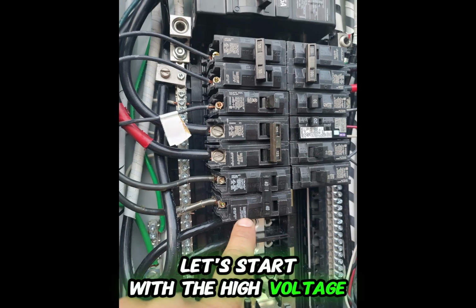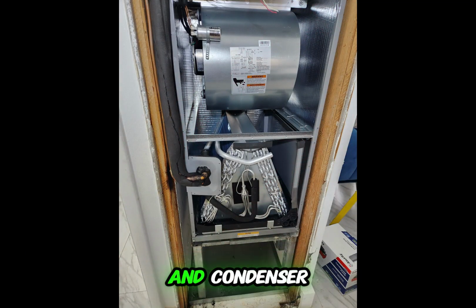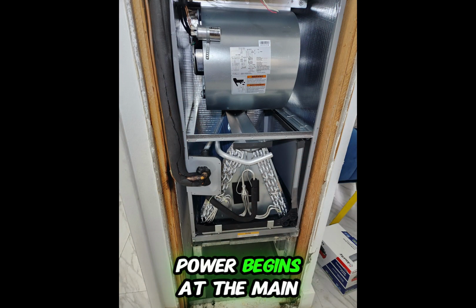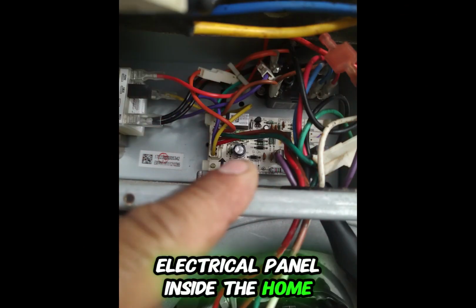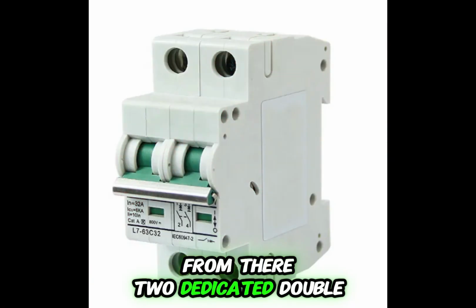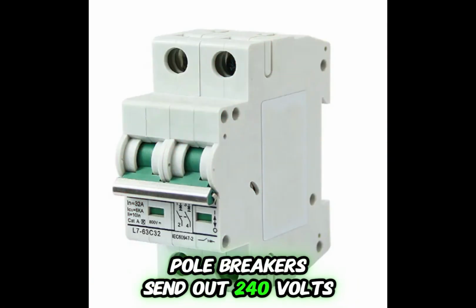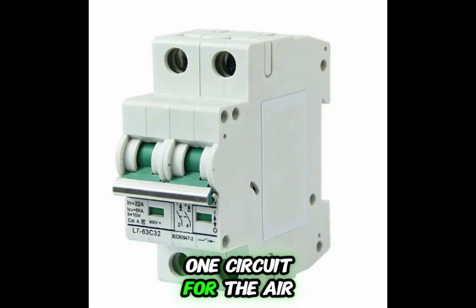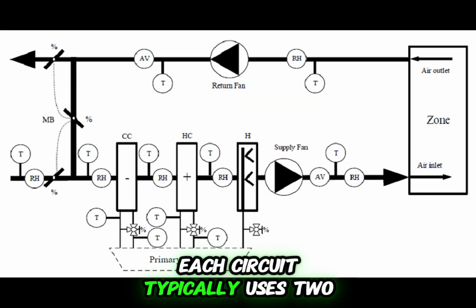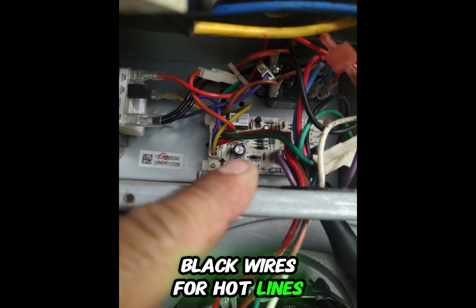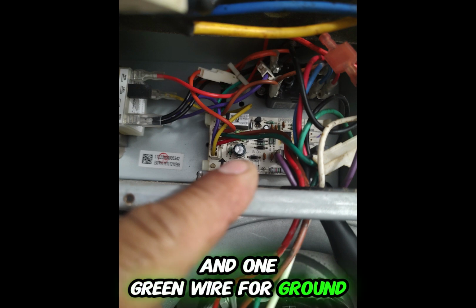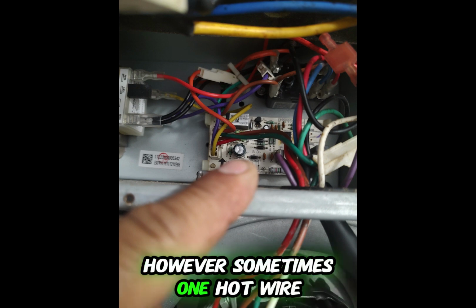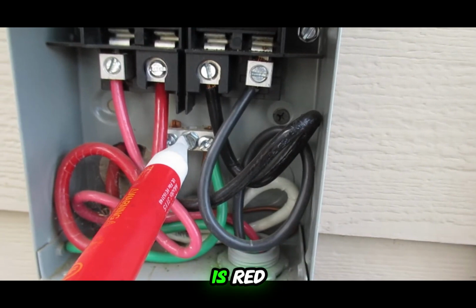High voltage, 240 volts. Let's start with the high voltage, which powers the air handler and condenser. Power begins at the main electrical panel inside the home. From there, two dedicated double-pole breakers send out 240 volts, one circuit for the air handler and another circuit for the condenser. Each circuit typically uses two black wires for hot lines and one green wire for ground. However, sometimes one hot wire is black and the other is red.